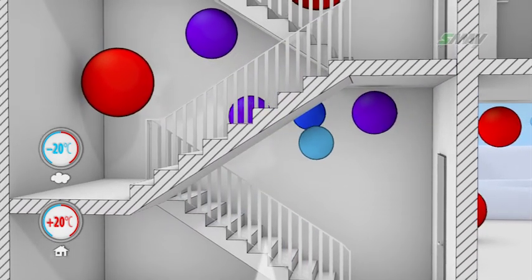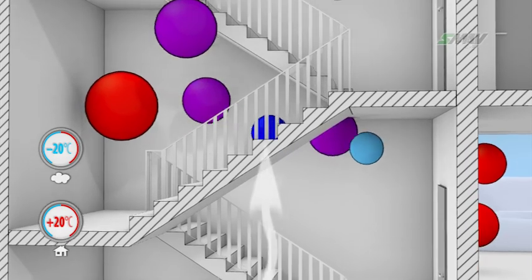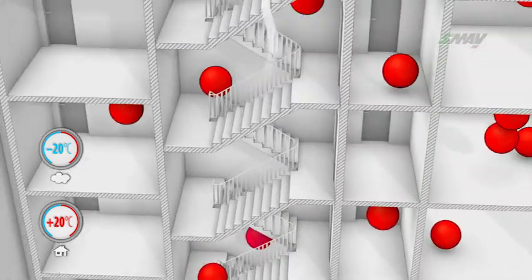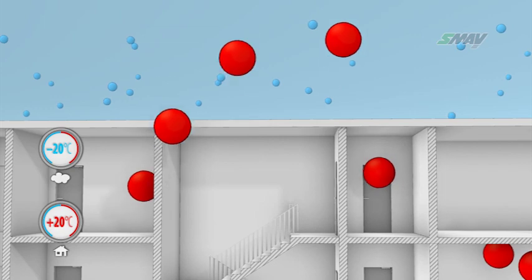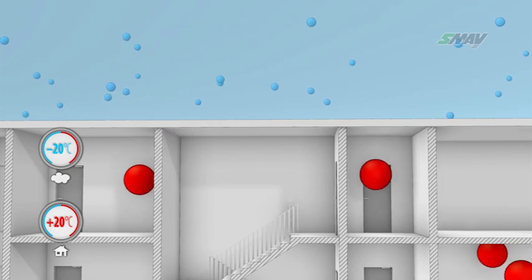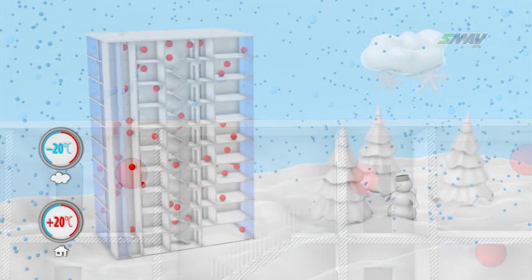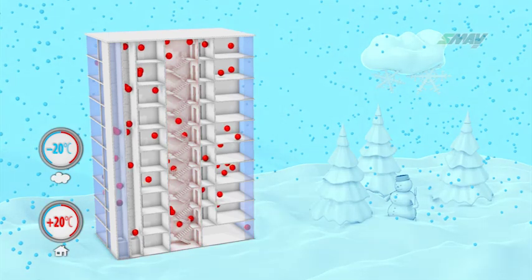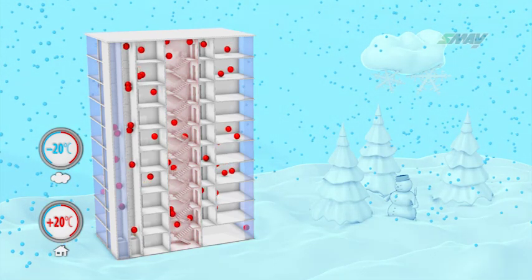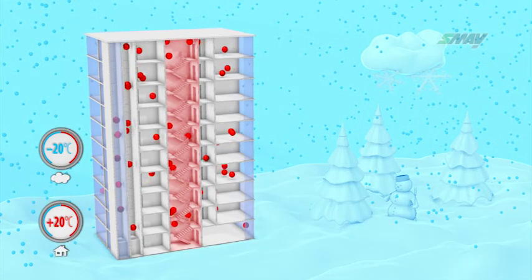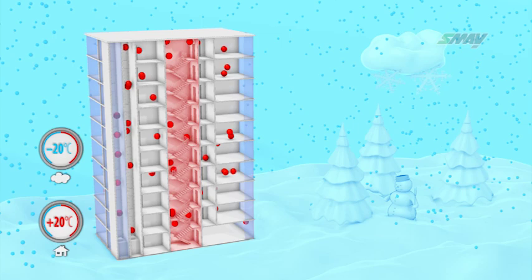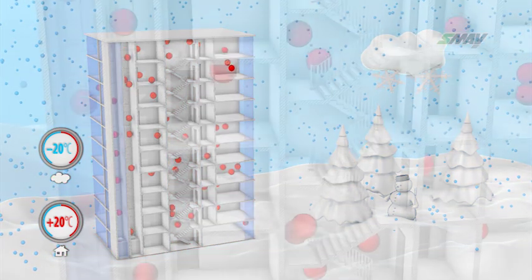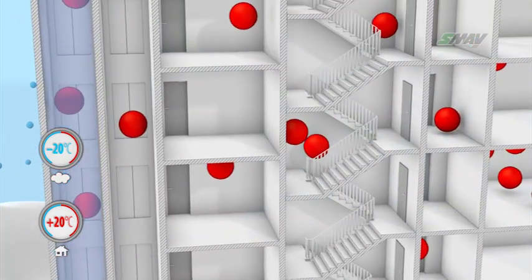If the stairwell is not airtight, or a window or doors are open at the building entrance level, the stack effect will always occur if there is a difference in air temperature between the stairwell and outside. If the stairwell is located in the interior of the building and not connected with the atmosphere, the stack effect will occur immediately once pressurization begins.